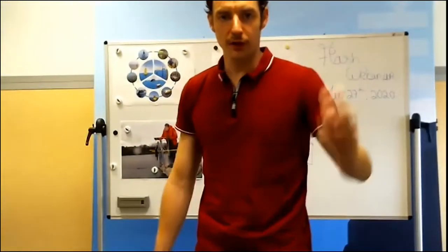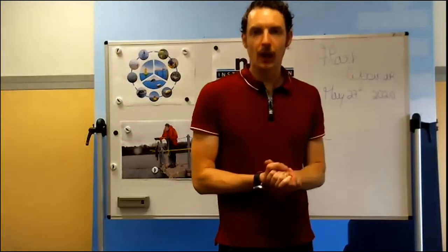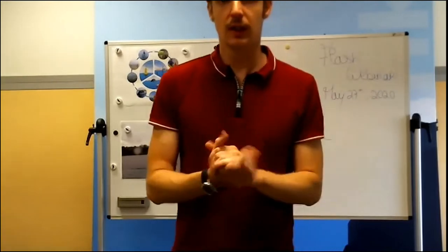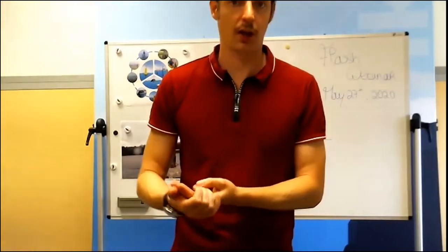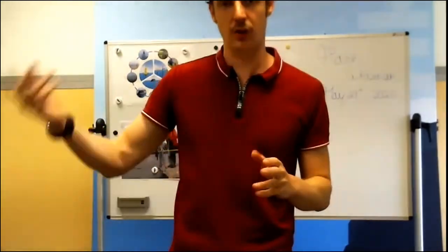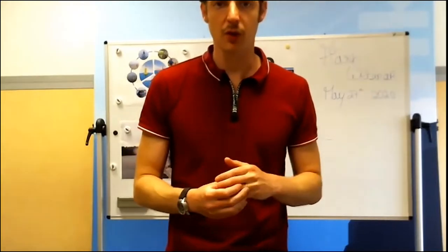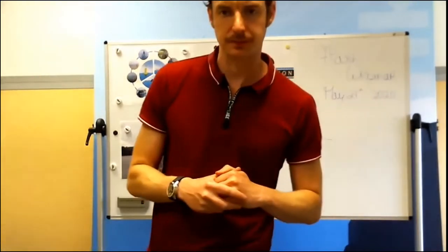Okay, frequency acquisition. I will answer the one about the frequency acquisition and the plan for additional sensors. The acquisition frequency of the sensor is about 1 Hertz, as far as I know, and except if you remove the sensor, as I say, and use the WiMo just for the pressure, I can have a higher frequency. But the frequency starts at about 1 Hertz, and then you can go to lower rates. It might be 2 Hertz with some of the sensors. The optical sensors might take a little bit more time to stabilize the measurement.